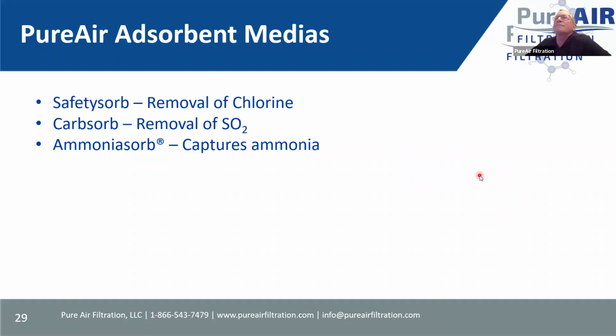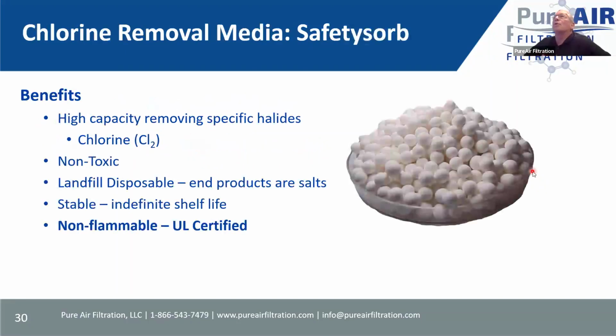Some of the common medias that we use for the gases: we use Safety Sorb for the removal of chlorine, Carb Sorb, or actually also Safety Sorb 2, for the removal of SO2, and Ammonia Sorb to capture ammonia. Chlorine removal media, again, Safety Sorb. High capacity, removing specific chlorine. It is non-toxic. Again, it's landfill disposable. End results are salt, or like I said earlier, a harmless salt compound. It's stable, with indefinite shelf life unless it comes in contact with chlorine or water or is crushed. It's non-flammable, UL certified, and that's very important when it comes to chlorine scrubbers.